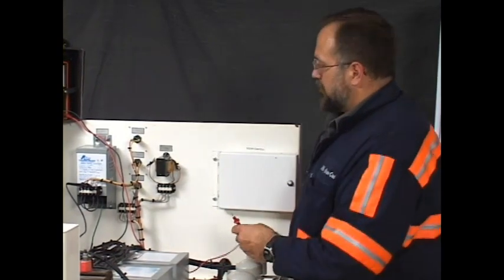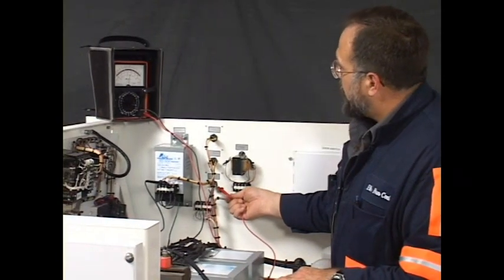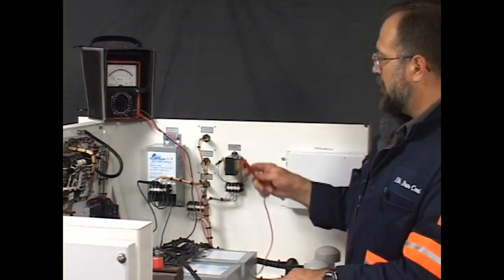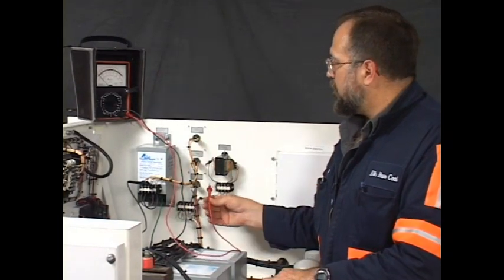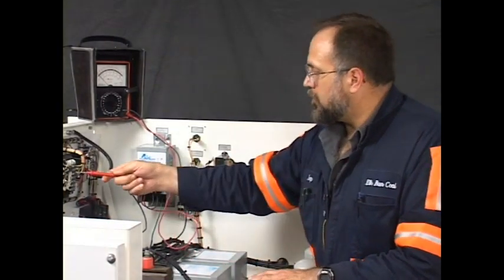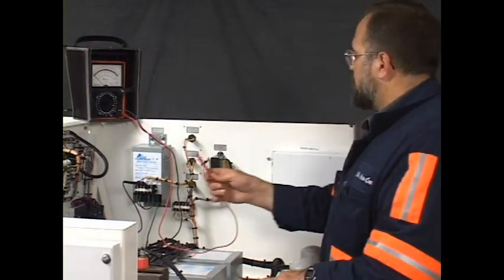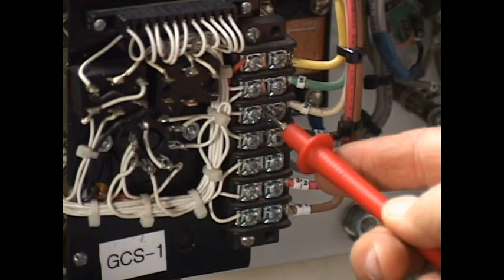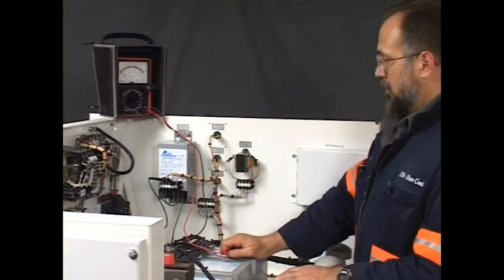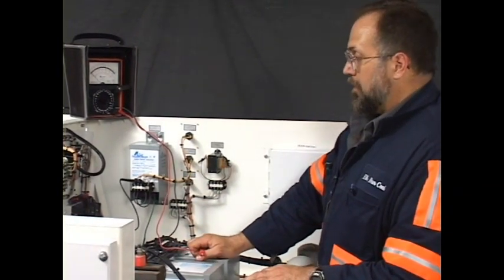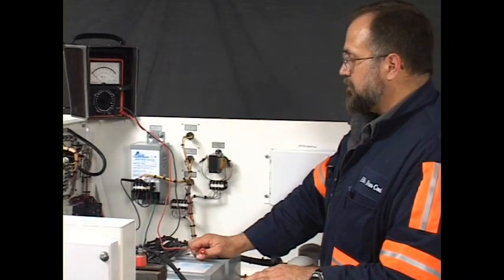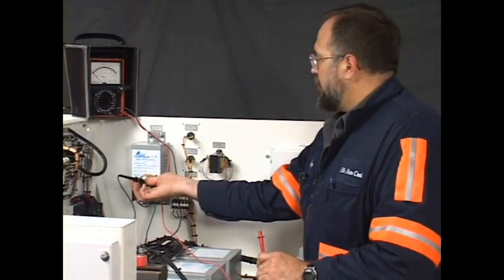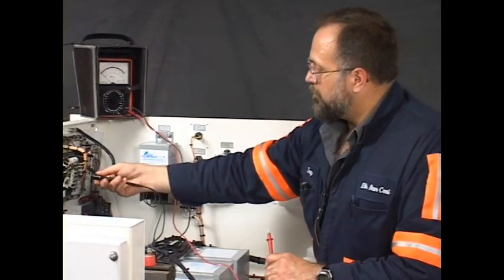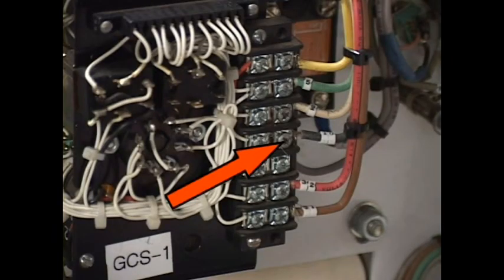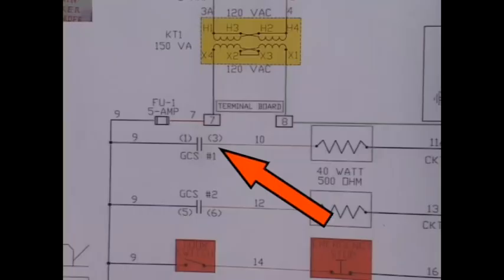We don't have a bad fuse though. We've got a good one. And it goes to wire number 9. From there, we're going to be following wire number 9 to terminal number 1 of GCS 1, wire number 9, and we have continuity. And with the power off and those relay tips open, we can't read any farther without moving our meter. So I'm going to move my black probe to wire 10. That's on the terminal number 3 on the load side of the GCS1 contact right there.